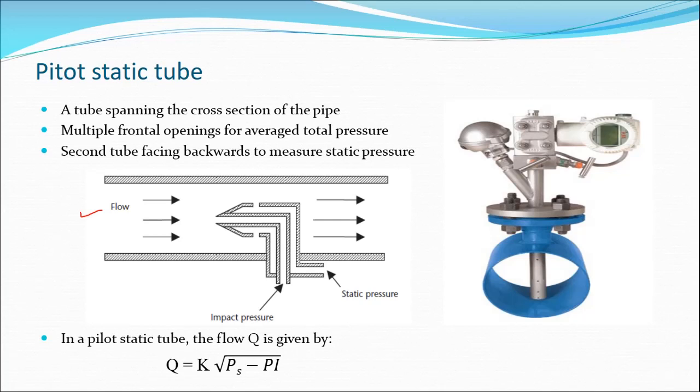Basically, the pitot static tube is an alternative method of measuring flow rate, but has a disadvantage in that it really measures the fluid velocity at a point, because the velocity varies over the cross section of the pipe. The pitot static tube should be moved across the pipe in order to establish an average velocity, or the tube should be calibrated for one area. Other disadvantages are that the tube can become clogged with particulates, and that the differential pressure between the impact and the static pressures for low flow rates may not be enough to give the required accuracy, but the differential pressure in any of the above devices can be measured.